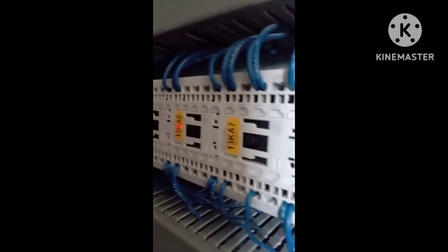You can see the PLC input output. Just now this 13K2 is not holding, but when we start the machine after pressing the push button, then pin number 6 of the digital output of this PLC will turn on this 13K2. It is only possible when there is no error on the machine, because the watchdog on the PLC is continuously monitoring its output. If there is some safety fault or discontinuity of emergency, in that case this will not allow it.